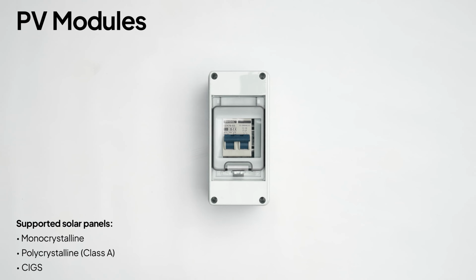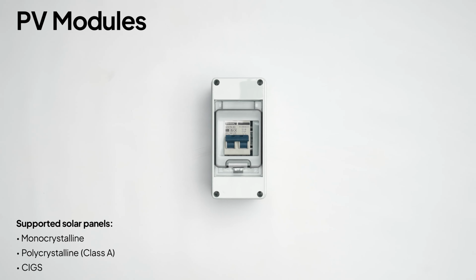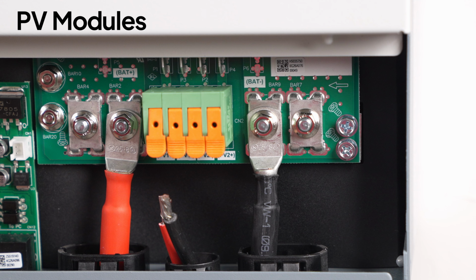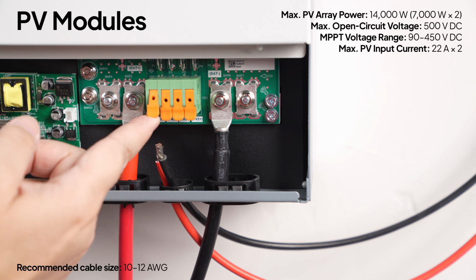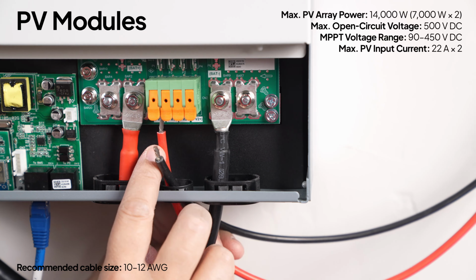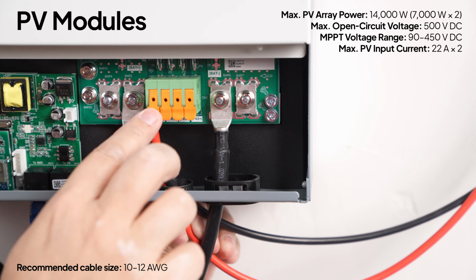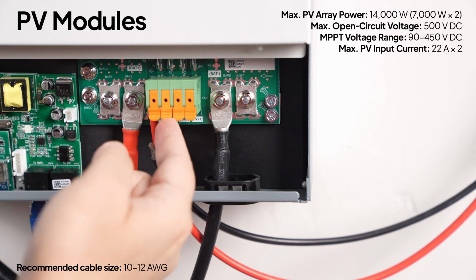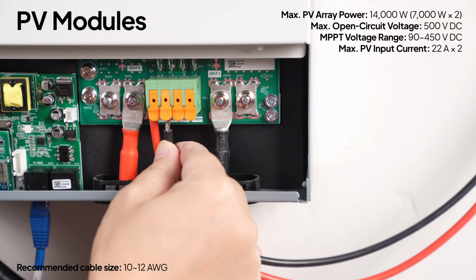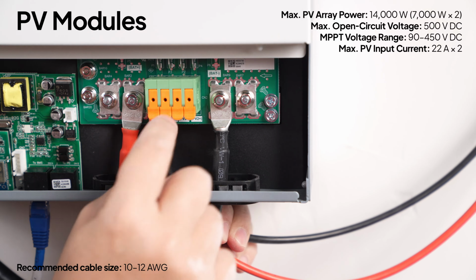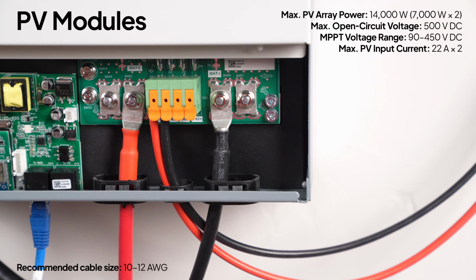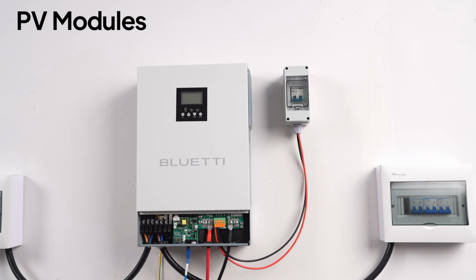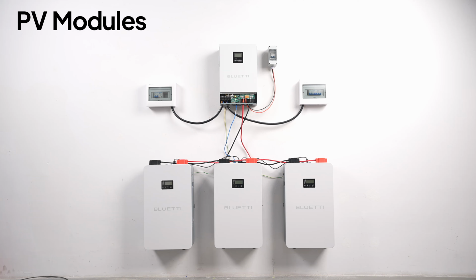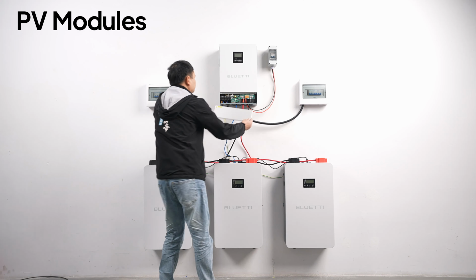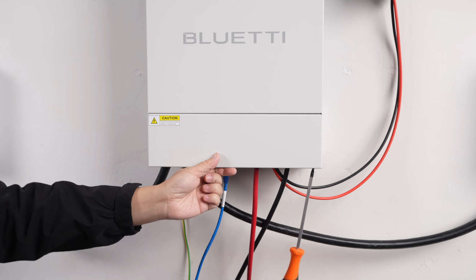Finally, wire the solar modules. Install a DC circuit breaker first. The inverter supports 2 PV strings. Follow the panel specs. Use 10 to 12 AWG cables, and strip 11 to 13 mm of insulation. Insert the cables into the PV inputs with the correct polarity, and lock them securely. Once all connections are verified, put the bottom cover back on.